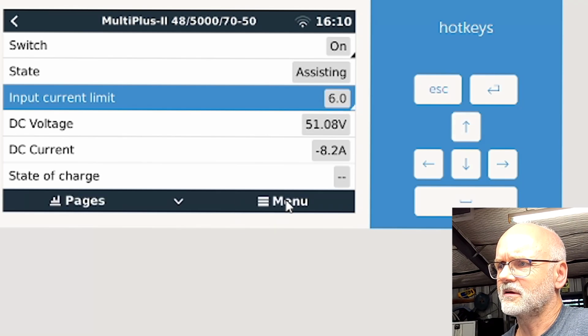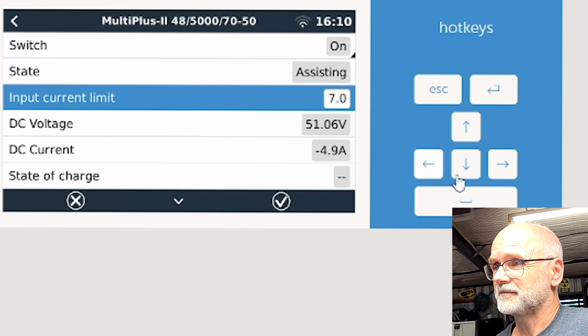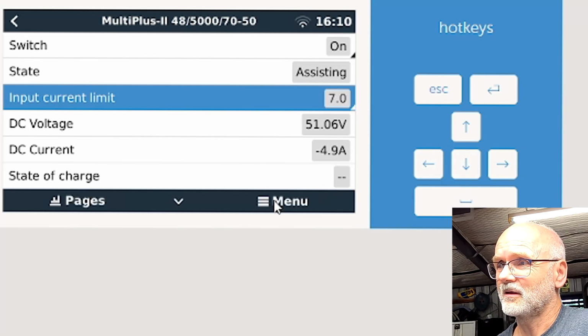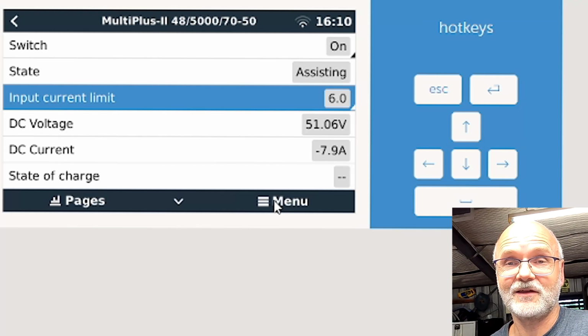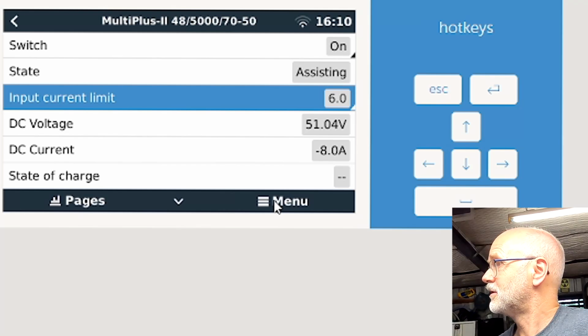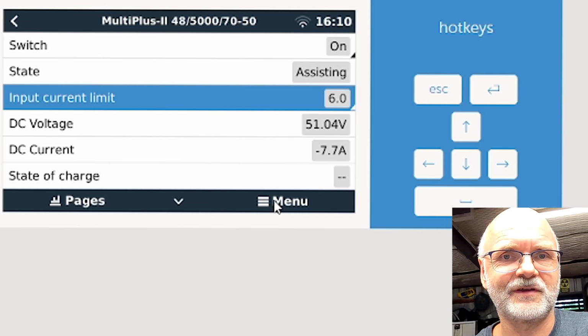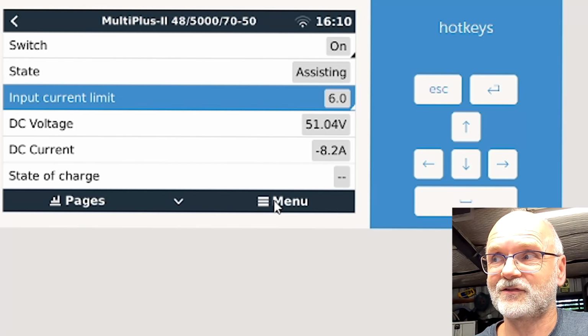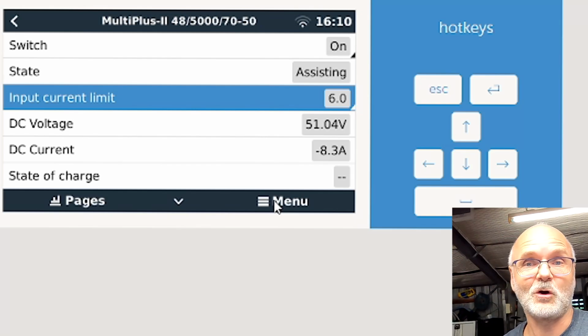7 amps - see, it takes over 7 amps. Obviously I cannot go lower than 6. 5.5... no, 6 seems to be the lowest we can set in the Multiplus. Bummer. Well, it is fine for our system here, because the Phoenix can deliver 3 kVA, so 6 amps is totally good.